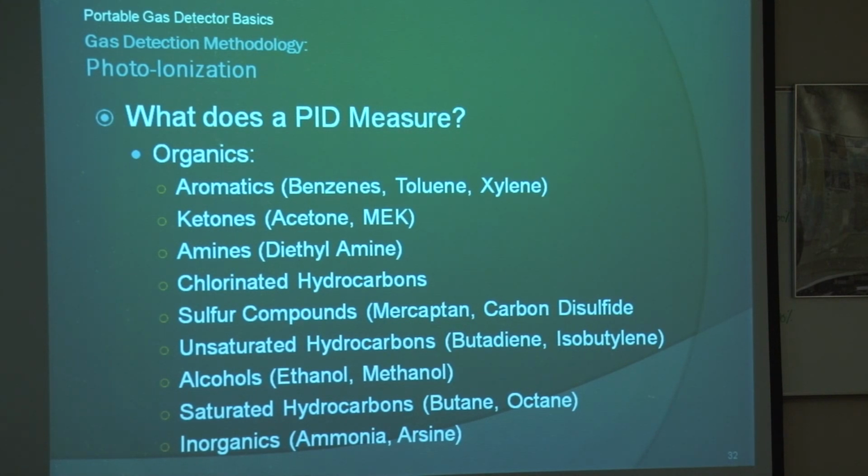Unsaturated hydrocarbons, alcohols, your ethanols, methanols, saturated hydrocarbons, and inorganics like ammonia and arsine. And that's where, if we go down range, what's going to alarm first on our ammonia? Just knowing about what we talked about on our monitors right now, Aaron. Is it going to alarm for VOC or is it going to alarm for LEL? What's lower? Is your IDLH for ammonia... Oh, it's going to alarm on the VOC, right? Yeah, because the alarm limit for VOC is 100. Right. And 100 parts per million of ammonia is going to kill you right now, but it's not flammable yet. Correct. Okay?